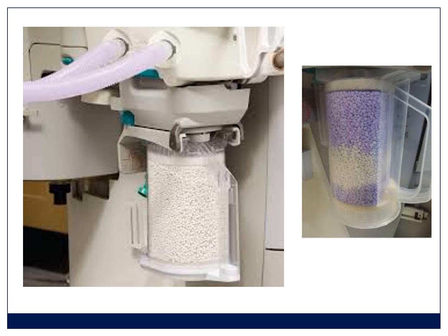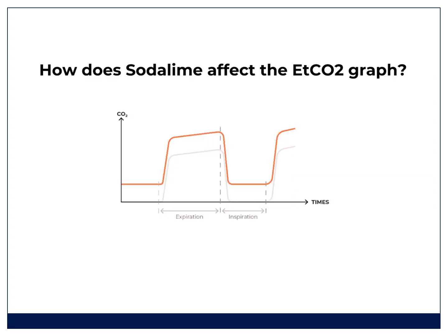Now, the other way of knowing that your soda lime is exhausted is just to look at the capnography, and you'll see that you start to get rebreathing. So that baseline CO2 during inspiration doesn't go back to naught. And that's basically showing rebreathing, and it's one of the signs of soda lime exhaustion. You're not removing that carbon dioxide from the circuit anymore.